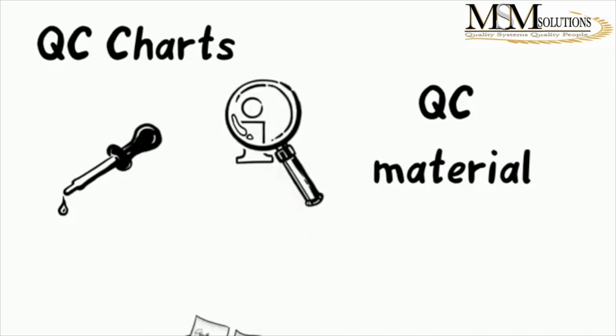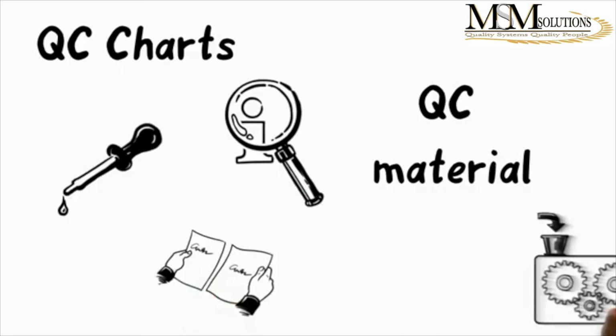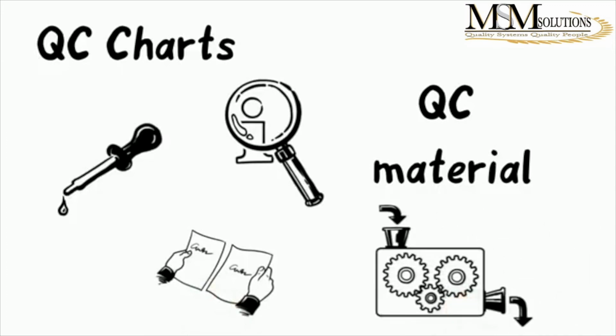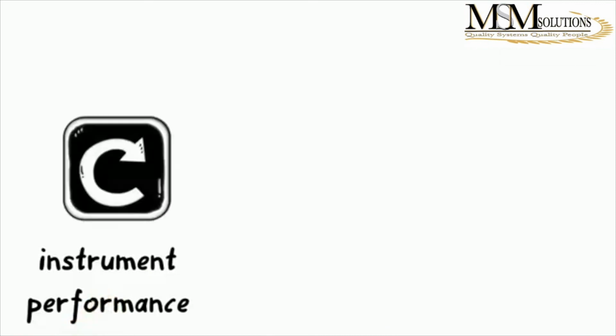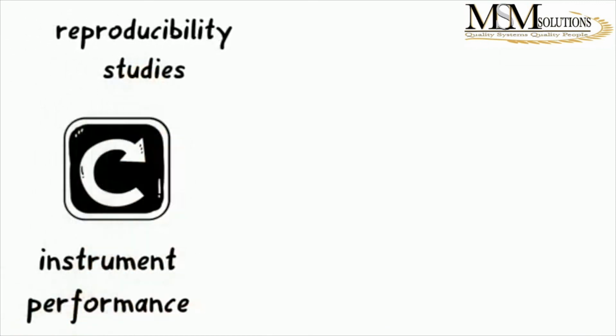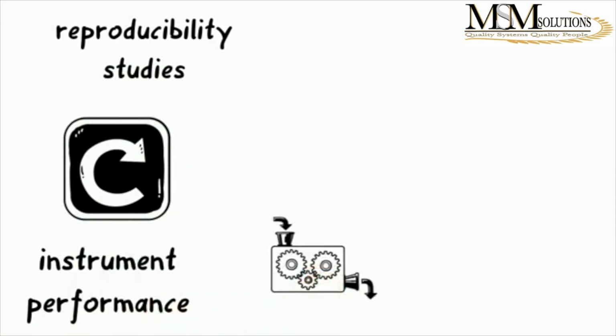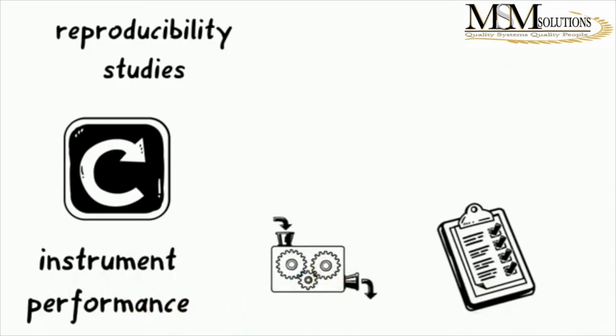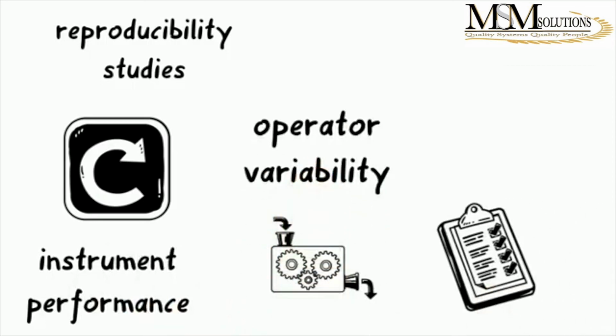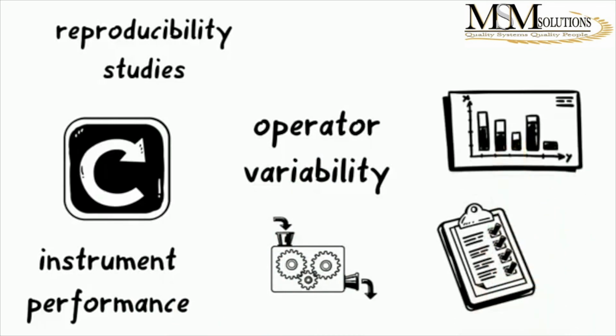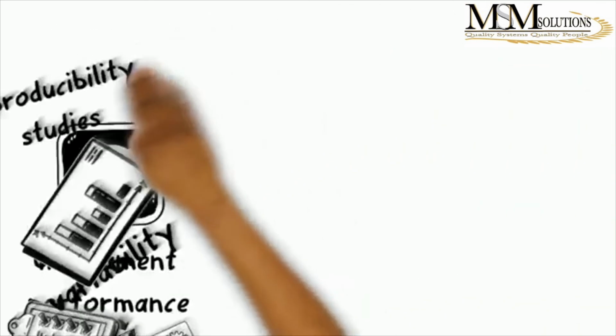You can use it for comparison of results. You can use it with method development. If you're developing a new method and you have a known value of your QC, when you use it there, it will give you a guide if your method is working or not working. Instrument performance test, repeatability and reproducibility studies. These are some of the data points you would need if you were to do a method validation exercise. You can use it as a check sample, or even to check your operators, operator variability. You can give it to different operators and see the different results, and be able to see if everybody is doing the same thing, or if there's differences, and maybe there's a training issue that you need to look at.